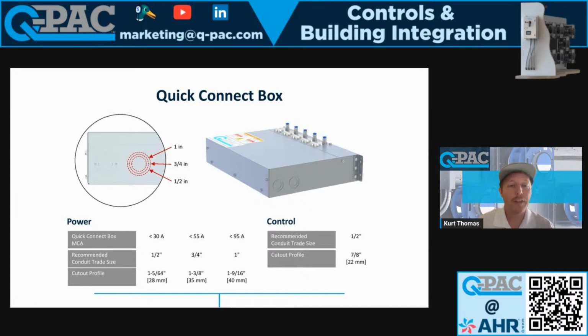Everything's pretty self-explanatory. I think we have 4 knockouts, 2 on the top, 2 on the bottom. You'd need to run your power and your controls in separate conduit. If you don't, then you may have some noise on some of those control wires just through induction. So we do recommend running 2 runs of conduit, 1 for power and 1 for controls. It doesn't matter how many fans you have in your system. It's just 1 run of power and 1 run of controls, which makes it a lot easier on your electrician. So if they quote you for a full day's worth of work, then you can tell them that I said that's not true. It should only take them a couple hours.